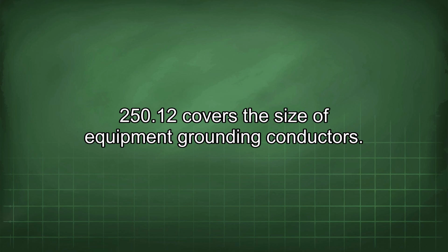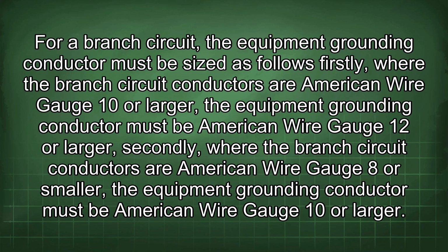250.12 covers the size of equipment grounding conductors. For a branch circuit, the equipment grounding conductor must be sized as follows. Firstly, where the branch circuit conductors are American wire gauge 10 or larger, the equipment grounding conductor must be American wire gauge 12 or larger. Secondly, where the branch circuit conductors are American wire gauge 8 or smaller, the equipment grounding conductor must be American wire gauge 10 or larger.